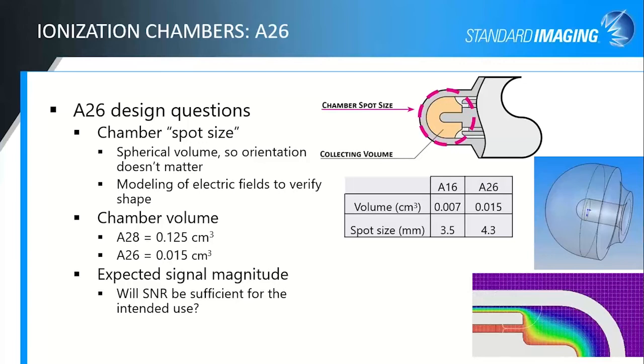Some of the things that we considered when designing this one, within those constraints of a well-behaved reference class chamber, was the chamber spot size. We wanted to make this a spherical chamber, or spherical active volume, in order to ensure that you're integrating over the same volume, the same space, no matter which orientation your chamber is in. We modeled the electric fields to verify that shape, and then we tried to make this as small as we possibly could. So the scanning chamber, the A28, is a 0.125 cubic centimeter chamber, like the rest of the standard scanning chambers. The A26 is down at 0.015. But the volume doesn't tell the whole story.